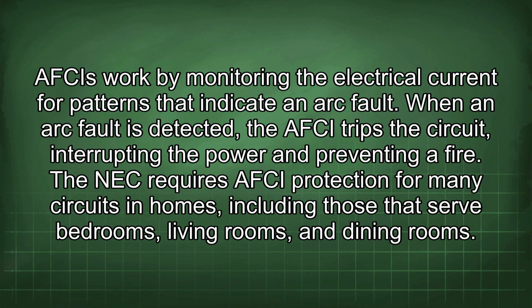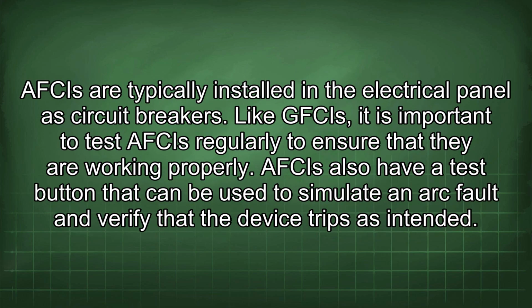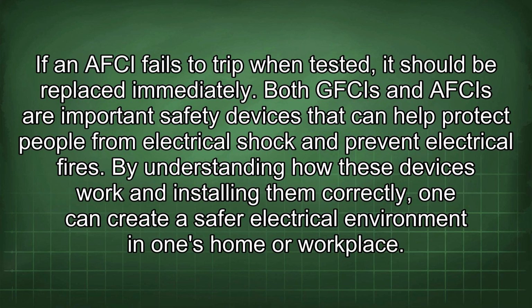The NEC requires AFCI protection for many circuits in homes, including those that serve bedrooms, living rooms, and dining rooms. AFCIs are typically installed in the electrical panel as circuit breakers. Like GFCIs, it is important to test AFCIs regularly to ensure that they are working properly. AFCIs also have a test button that can be used to simulate an arc fault and verify that the device trips as intended. If an AFCI fails to trip when tested, it should be replaced immediately.